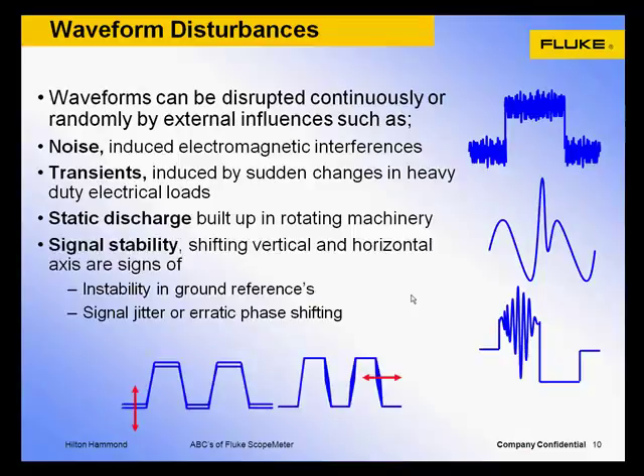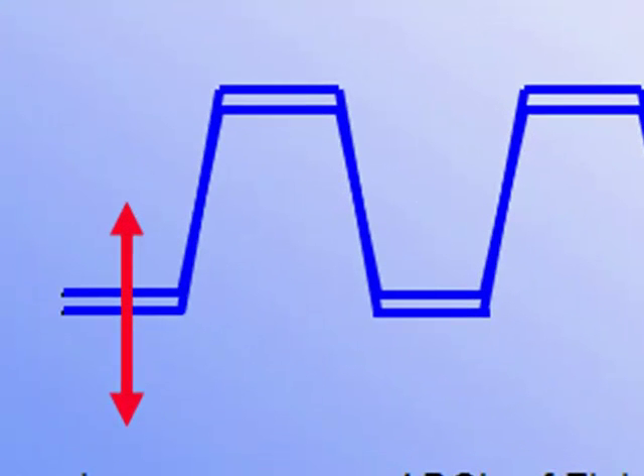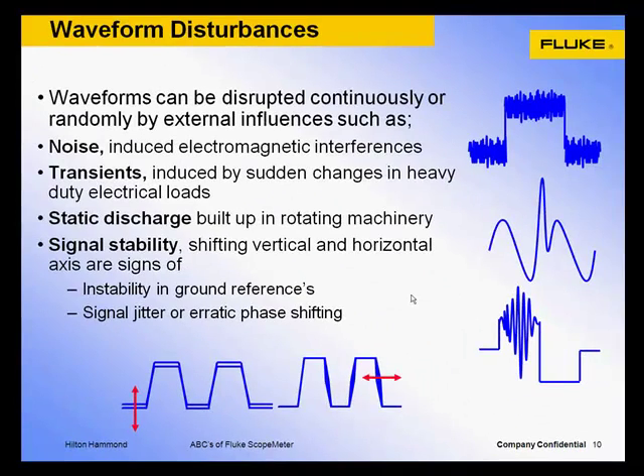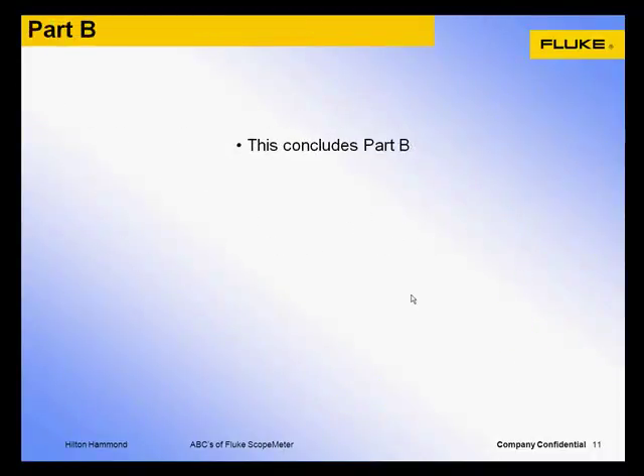Signal stability: check for shifting vertical or horizontal axes. Any instability in ground references or DC offset changes could indicate earth ground loop problems. Any horizontal time-related signal jitter or erratic phase shifting could be the result of problems in digital circuit clocks and signal transmission pathways. This concludes part B on analyzing waveforms. Next we will review some techniques and functions to capture intermittent random events.